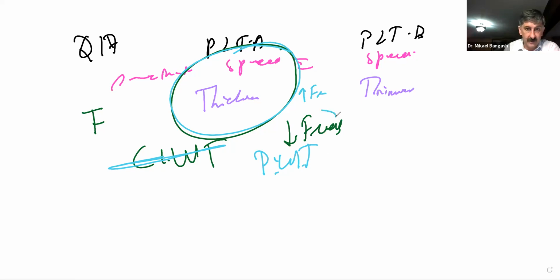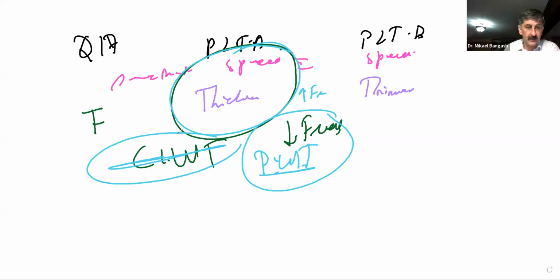Because question 16 was about a pulse wave transducer. Here it is false mainly because the transducer they talk about is a continuous wave transducer, where the frequency is not dependent upon the speed of sound in the PZT. It is not determined by the thickness of the PZT. It is determined by the frequency of the electrical signal.